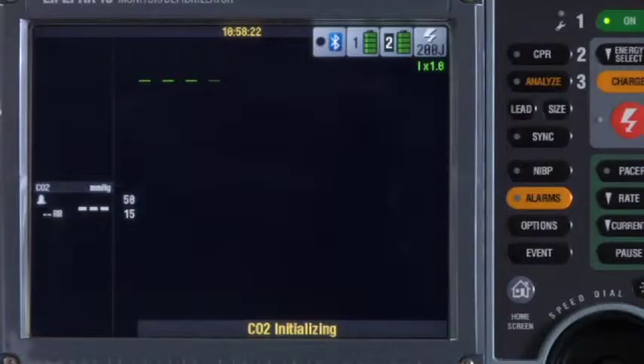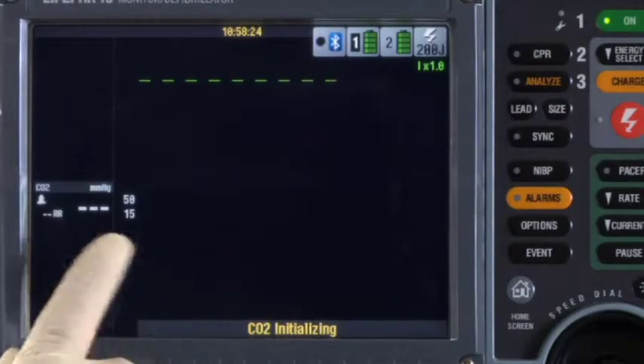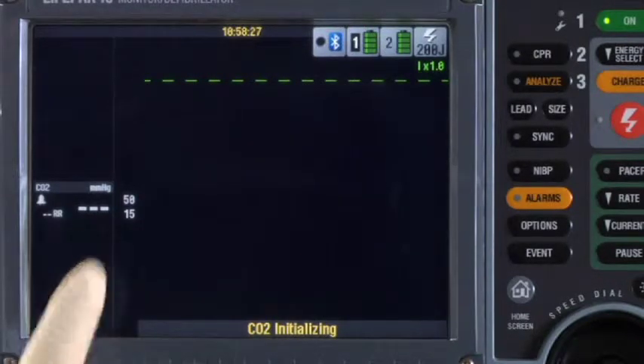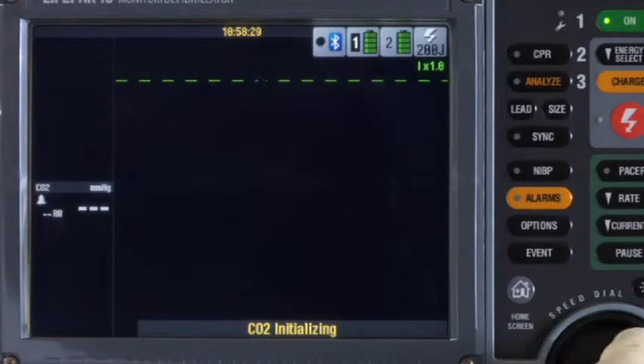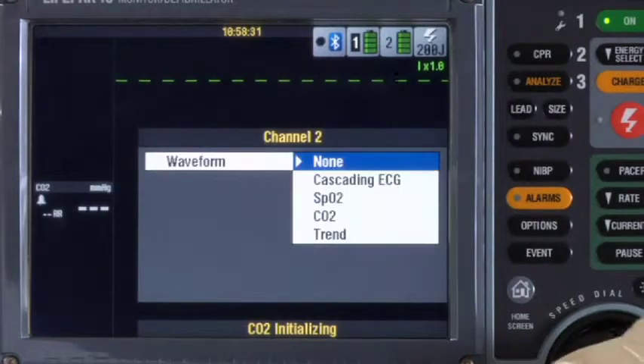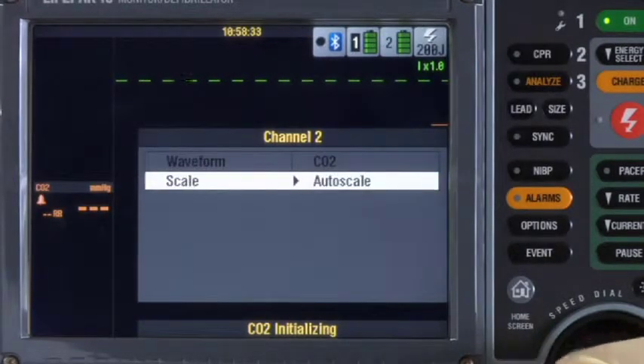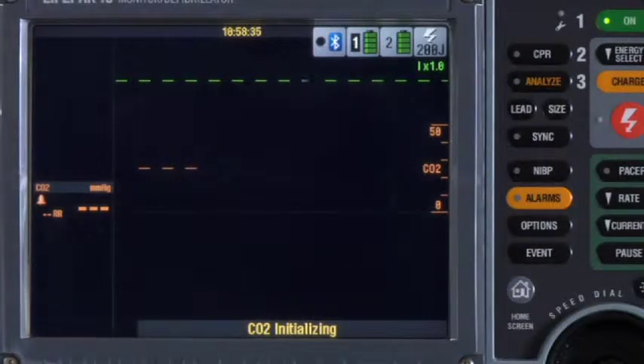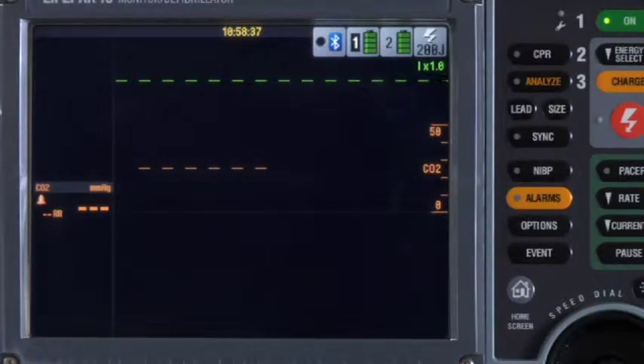There's a CO2 initializing message, and you see dash marks here for the respiratory rate. You can display the CO2 waveform in channel 2 or 3. Use the speed dial and select CO2 from the menu. The waveform will be a dashed line until the monitor finishes initializing. Then it becomes a flat line.